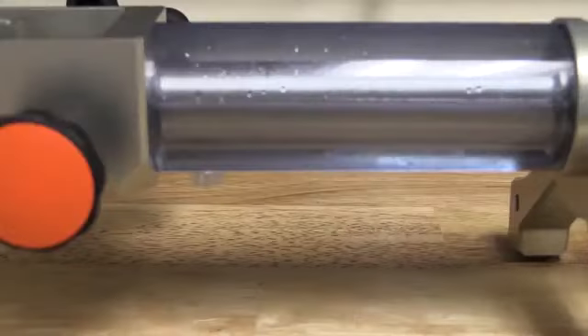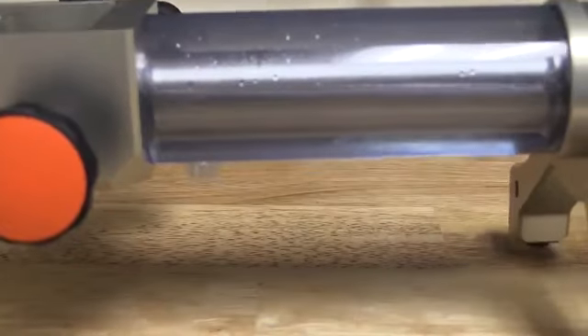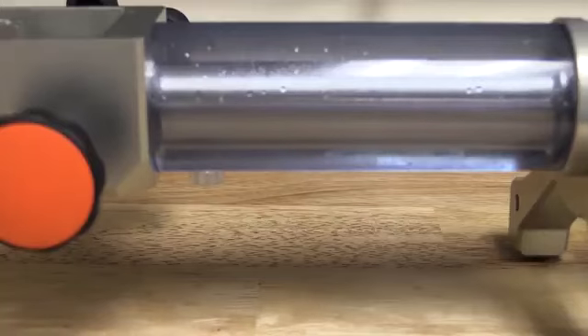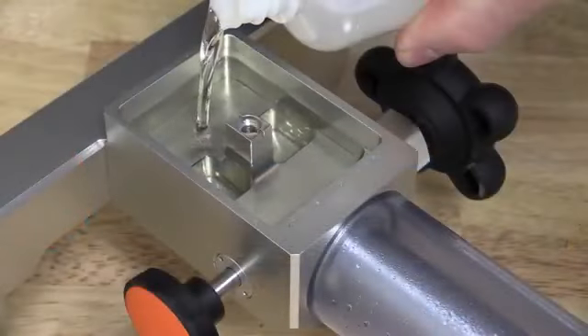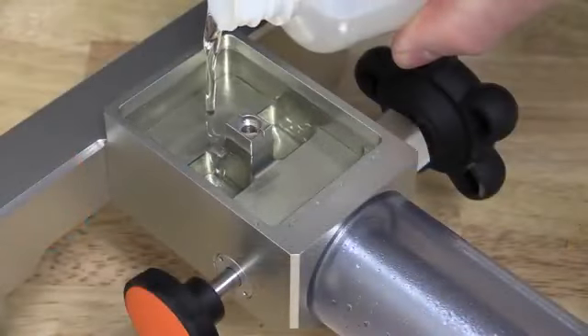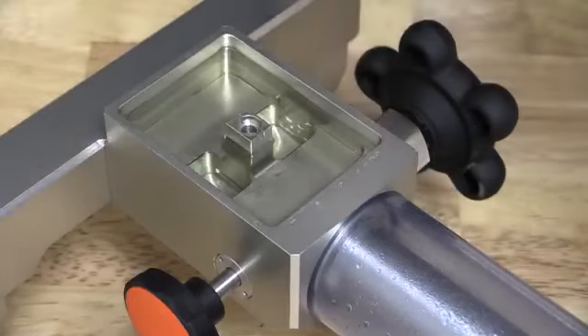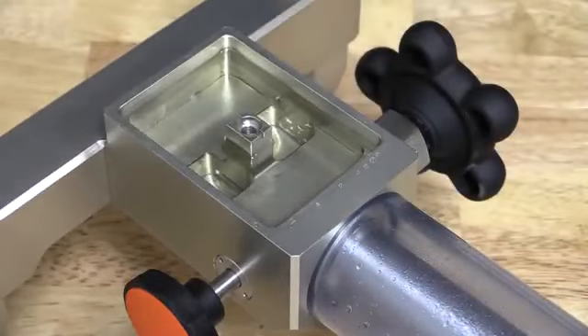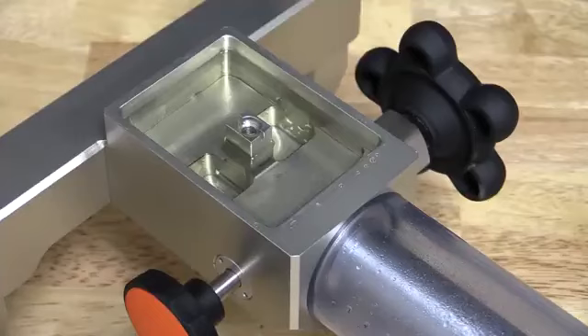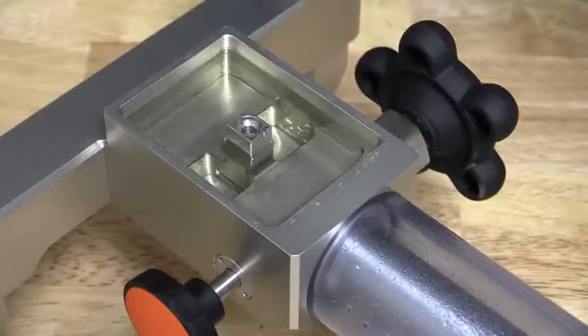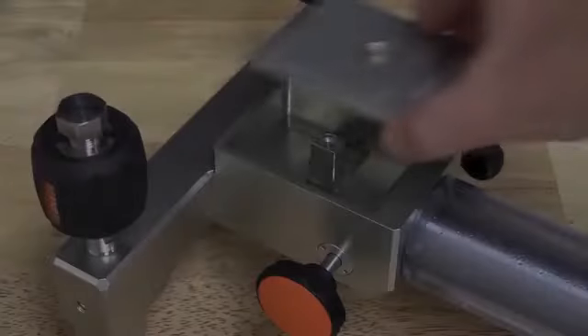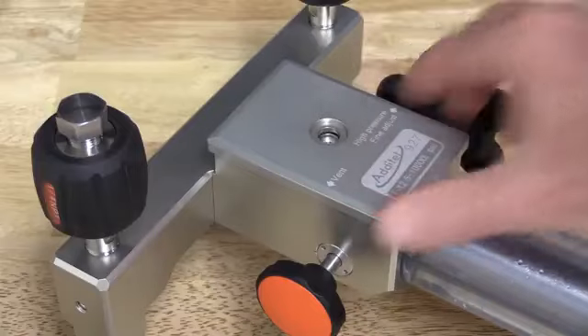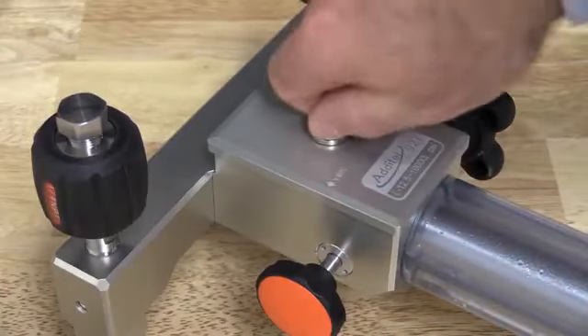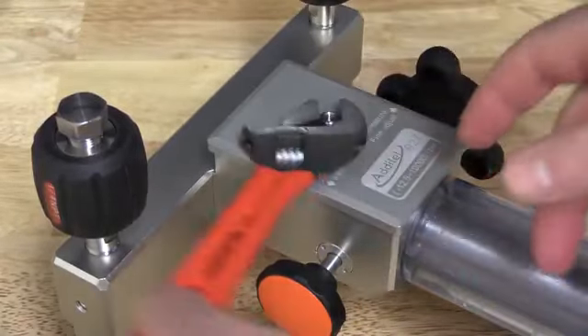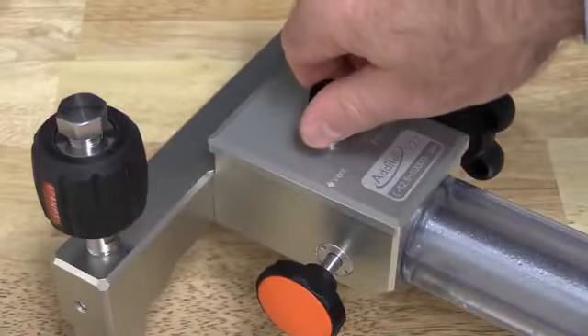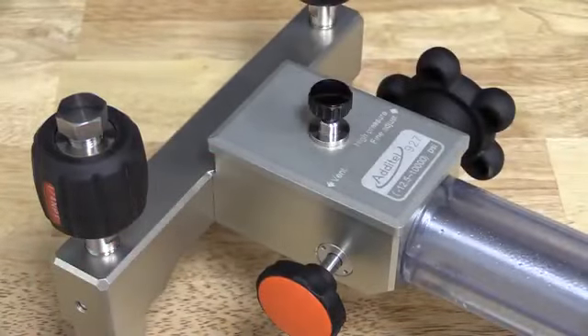We will want to add enough fluid until the clear liquid reservoir is about 2/3 full. Fluid poured into the reservoir tank will displace into the clear reservoir. This may take a few minutes to happen. Fluid may need to be added a second time to reach the appropriate level. Once we have the liquid reservoir 2/3 full, we can put the reservoir lid back on. We do this in reverse order of how we remove the lid.